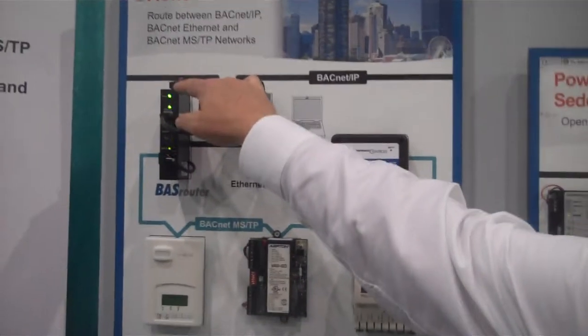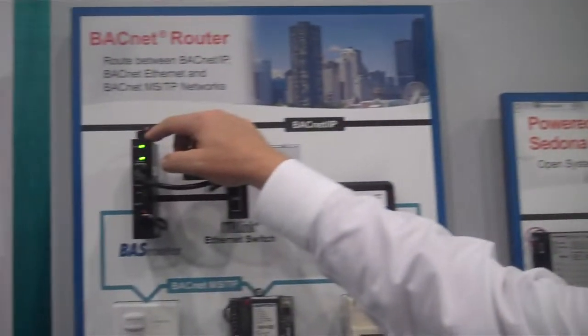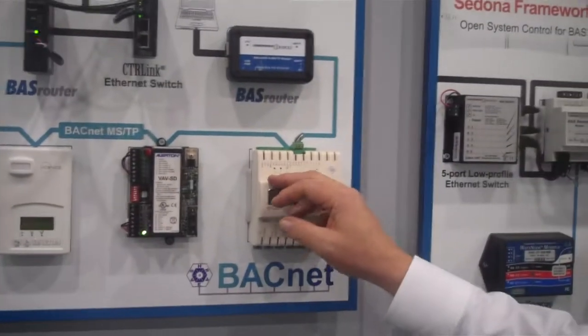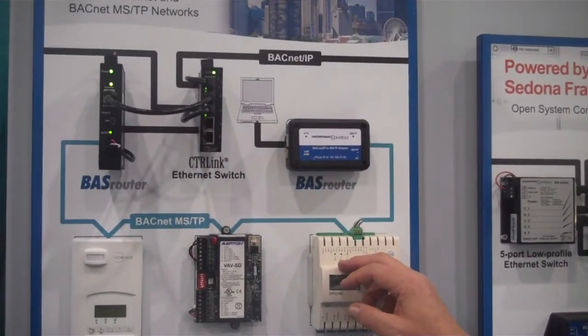Over here we have the BACnet IP to MSTP router. It's a very simple device that simply takes the BACnet IP packets, translates them to an MSTP packet, and vice versa.